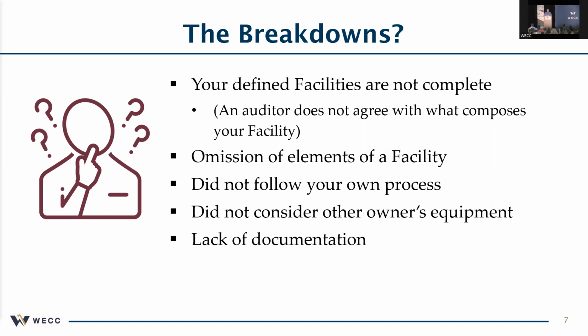The second bullet there, omission of elements in the facility, assumes you don't have a disagreement with the auditor, that you actually know what your facility is, but you just haven't walked down and validated, so you've left something out. You left a wave trap out, or you identified something but got the wrong rating for it, or you didn't follow your own process. We've seen a couple of cases where entities have actually improved their process, but they failed to address the fact that they have a whole bunch of facilities rated in accordance with the old process, and there was no transition allowed. So you can shoot yourself in the foot if you're not careful when that occurs. And they didn't consider other owners' equipment when looking at a jointly owned facility.